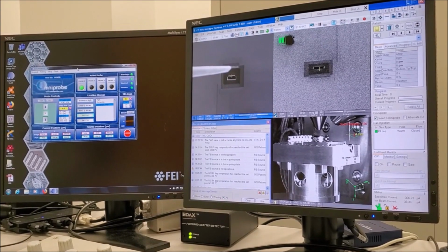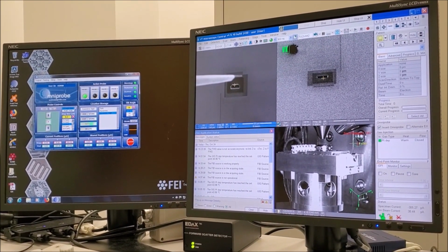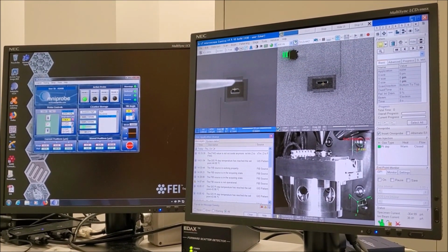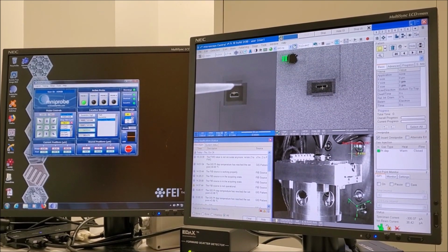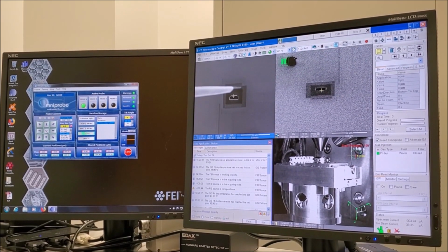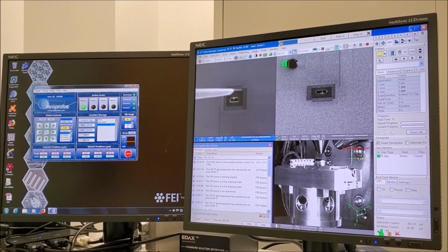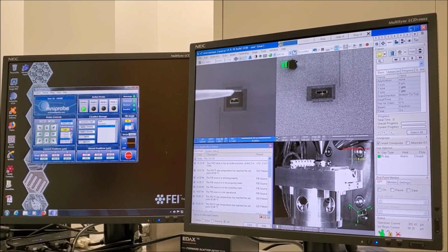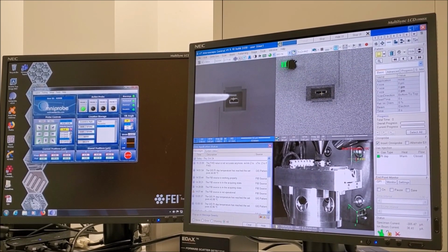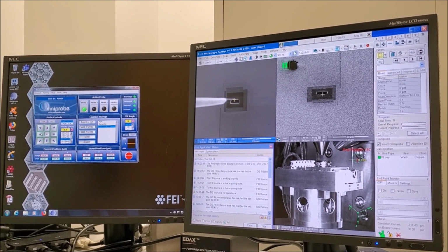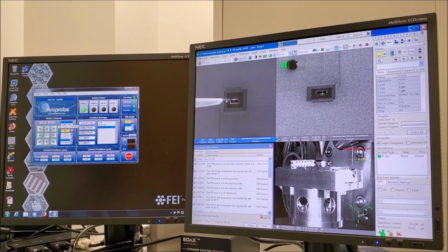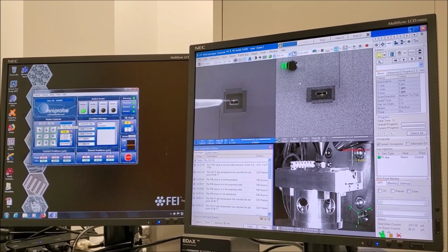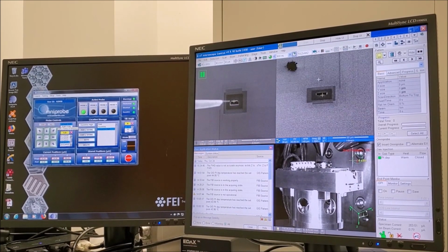In the AutoProbe software under probe controls, verify that stage frame of reference is selected. You can toggle between X, Y, and Z controls by selecting the middle square accordingly. Select the desired velocity from the list to the right of the probe controls. In this case, we have XY activated and we're using the electron beam image to move the OmniProbe so it is over the point of interest.